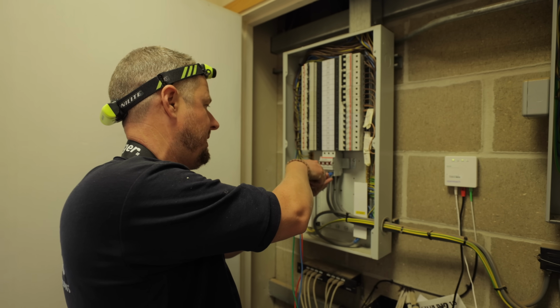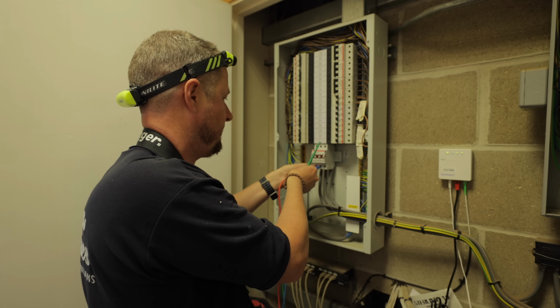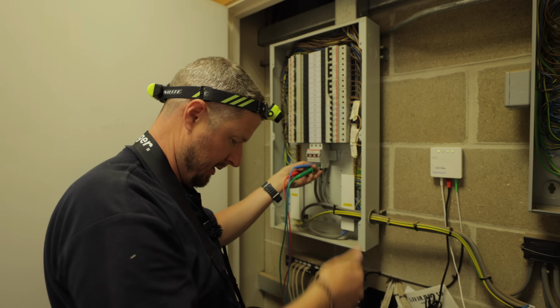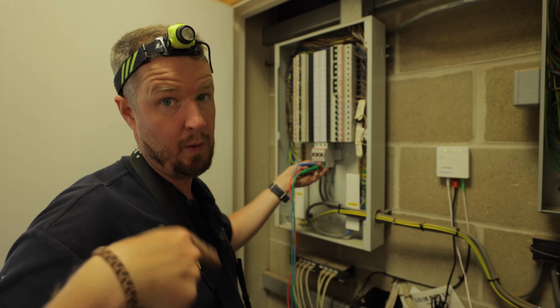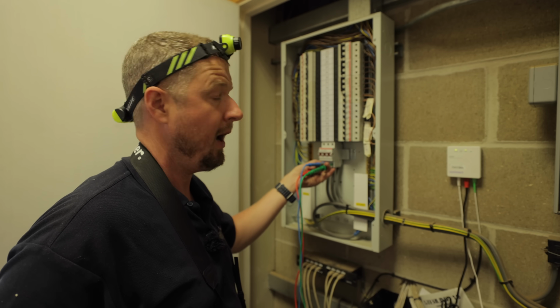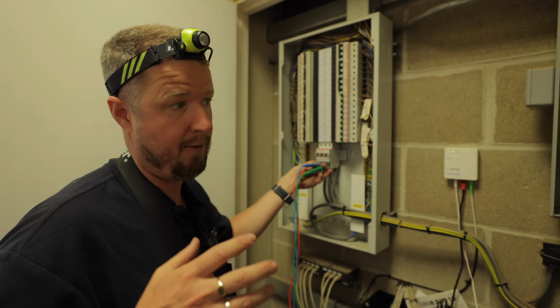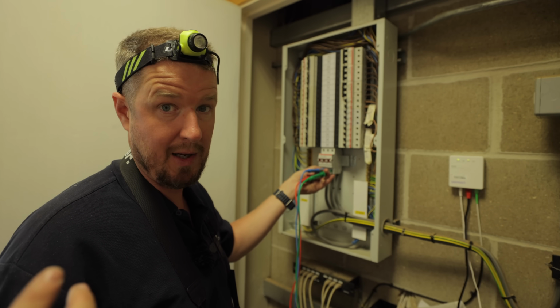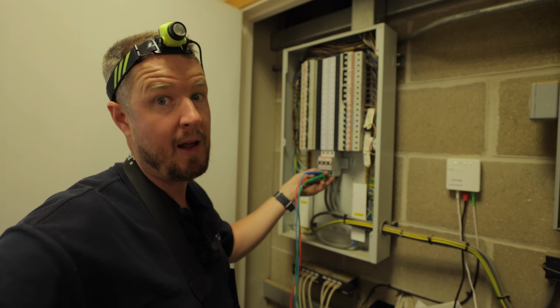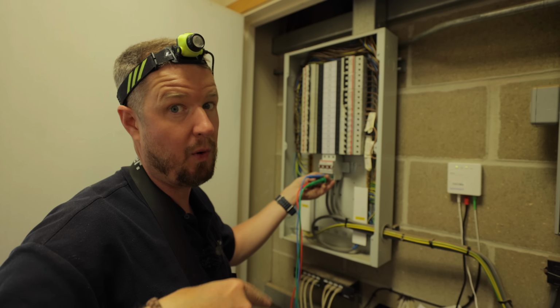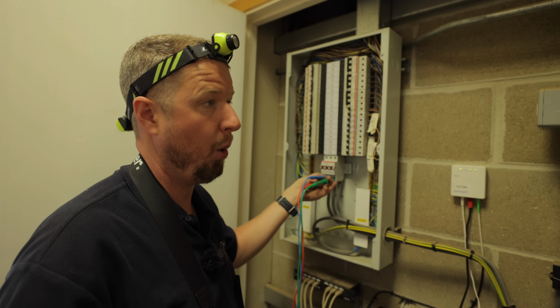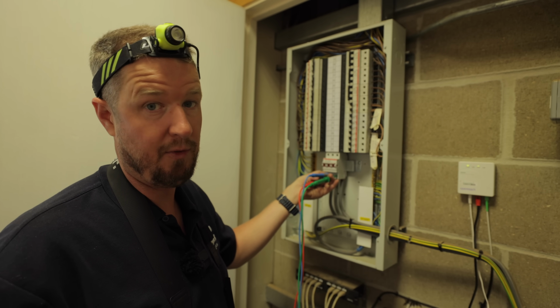It says 1, 2, 3, which is exactly what we want it to see. If we swap these 2 phases round, it's going to tell us it's down 3, 2, 1. So the phase rotation is reversed. And what that would cause, if there was a 3-phase electric motor in this place, is the motor would spin backwards, which could be quite dangerous. So phase rotation is important if you do have installations where you've got electric motors.